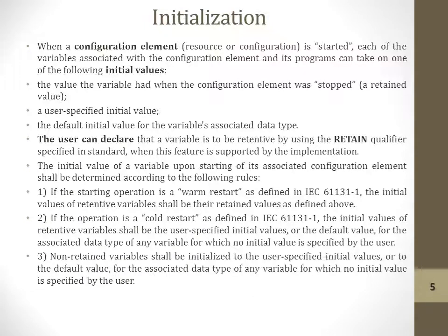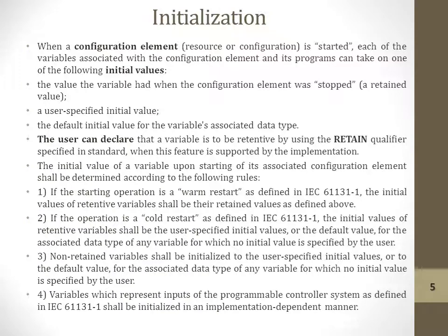Third, non-retained variables shall be initialized to the user-specified initial values or to the default value for the associated data type of any variable for which no initial value is specified by the user. And last, variables which represent inputs of the programmable controller system as defined in the standard shall be initialized in an implementation-dependent manner.